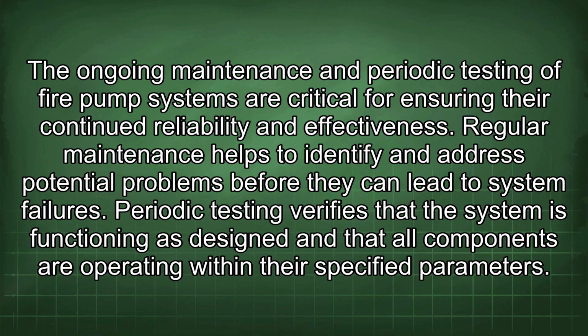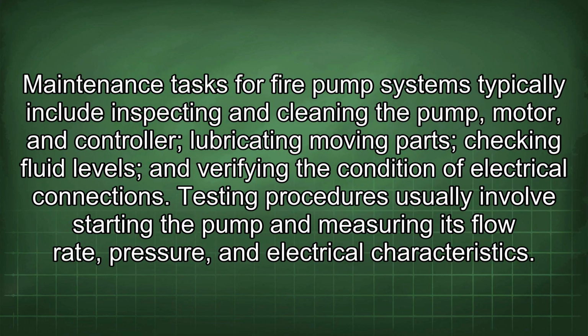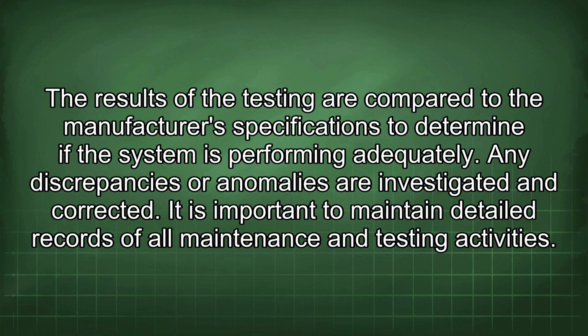The ongoing maintenance and periodic testing of fire pump systems are critical for ensuring their continued reliability and effectiveness. Regular maintenance helps to identify and address potential problems before they can lead to system failures. Periodic testing verifies that the system is functioning as designed and that all components are operating within their specified parameters. Maintenance tasks for fire pump systems typically include inspecting and cleaning the pump, motor, and controller, lubricating moving parts, checking fluid levels, and verifying the condition of electrical connections. Testing procedures usually involve starting the pump and measuring its flow rate, pressure, and electrical characteristics. The results of the testing are compared to the manufacturer's specifications to determine if the system is performing adequately. Any discrepancies or anomalies are investigated and corrected.